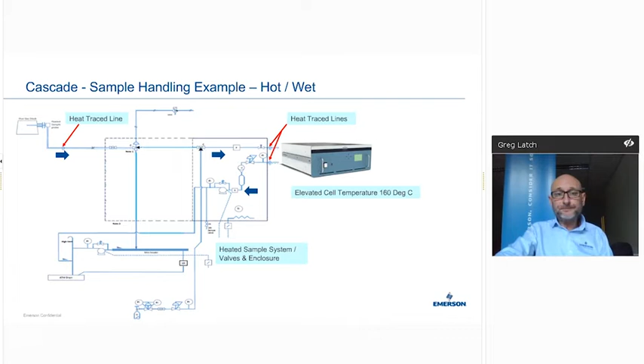This is over and above a fast loop system you may have on your takeoff point. We can actually run this analysis system at 5 litres a minute. So just to let that sink in and absorb for a little bit, it's a very high and fast flow rate for a measurement cell, 5,000 cc's in a minute. And based on a 1/4 inch line, with a 40 metre sample run, we can look at an update time without a fast loop of under 8 seconds. I'm quite excited by that, and by making that comment that, for example, SEMS measurements can definitely be used for process control.